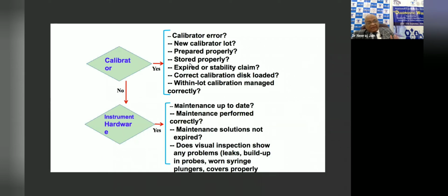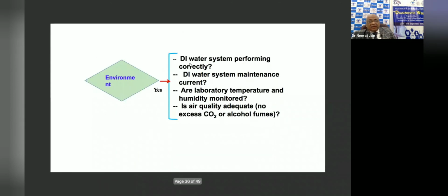Then instrument hardware: you are taking care of proper maintenance, daily maintenance, weekly maintenance, monthly maintenance. You have an official AMC or CMC with you, and whatever maintenance solutions and cleaning solutions you are using are not expired. And also visual inspection for problems: there is no leak or deposits in the probe, or torn tubes. All these things are not there, and everything is working in a proper manner. The cuvettes which you are using, if you are cleaning them, are cleaned properly, and scratches are not there. They are taking care of all these things related to hardware. And also the person who is operating your machine, who is taking care of all these things, shall be trained to take good care of all these aspects.